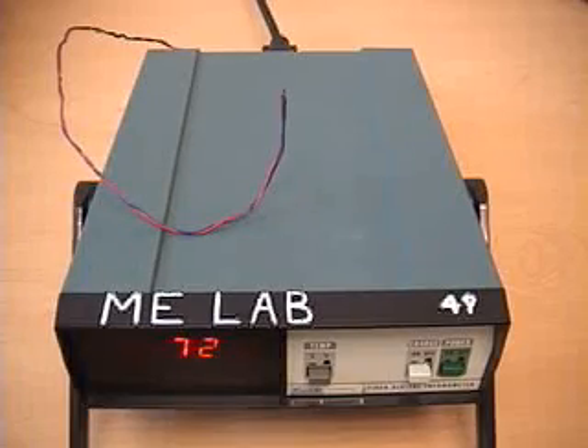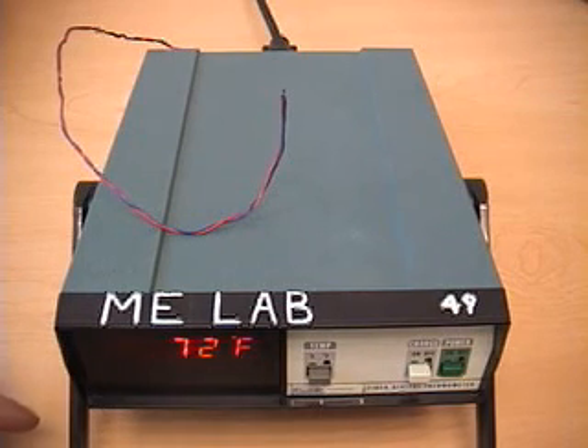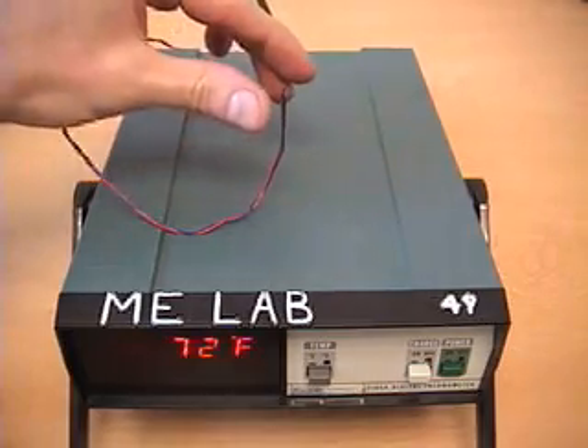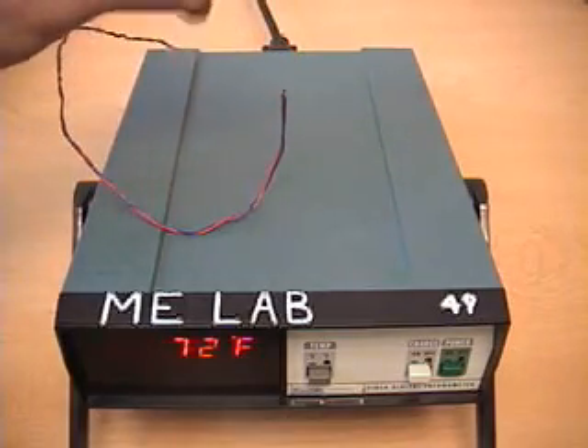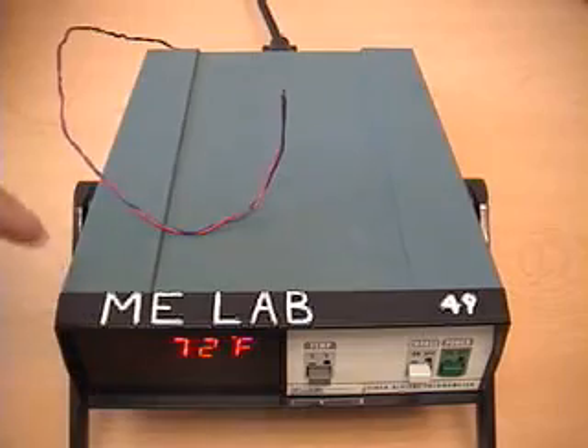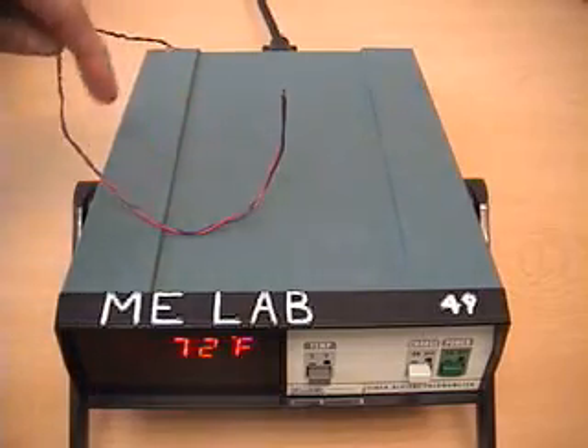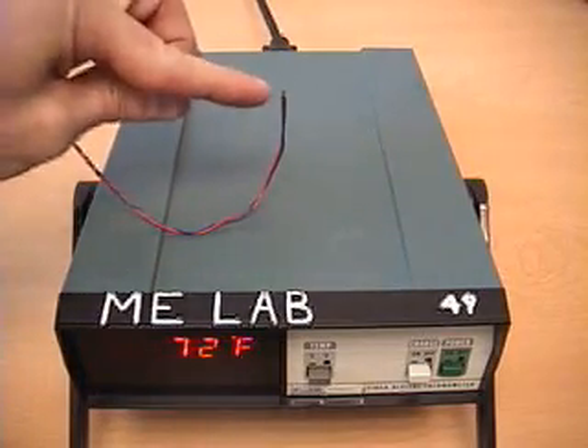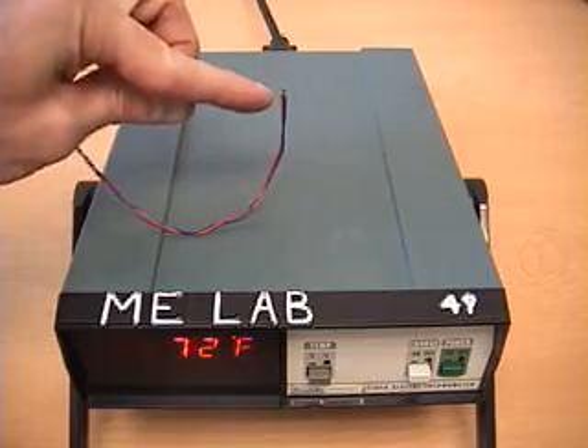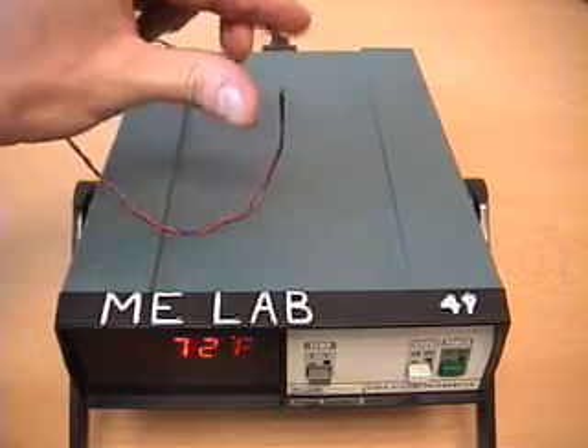As with many temperature measuring devices, you have to be aware of the delay between actual temperature changes and what is recorded by the device. So here, if I press my fingers to the measuring probe, my fingers are a lot warmer than room temperature, so the temperature will rise, but you'll see that it will rise slowly due to the time constant of the system. It takes a while for the thermal capacitance of the measuring probe to balance out with our applied temperature.